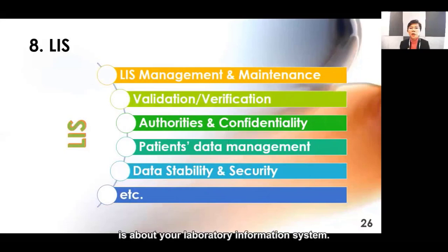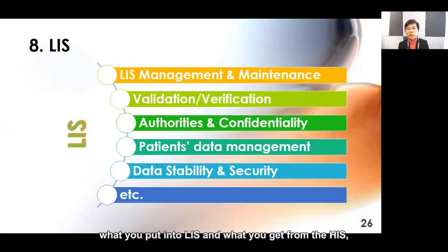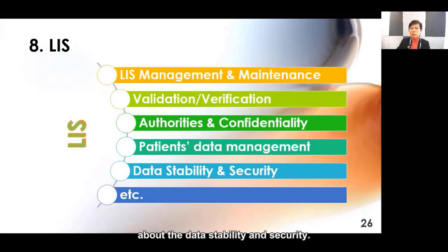The point number 8 is about your laboratory information system. It's important that you do the LIS management and maintenance, and also important for you to do the validation or verification of the software. What you put into the LIS and what you get from the HIS have to be the same. So you have to verify or validate this. And also you have to think about authority and confidentiality. So you have to have passwords and also user cards. So it's for your consideration. And also you have to think about patient data management. And exactly you have to be careful about data stability and security.